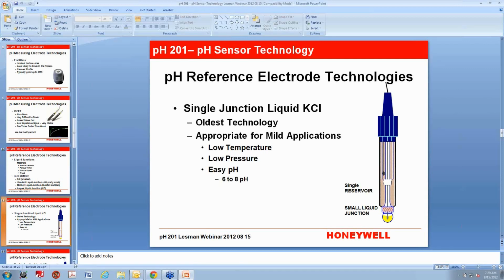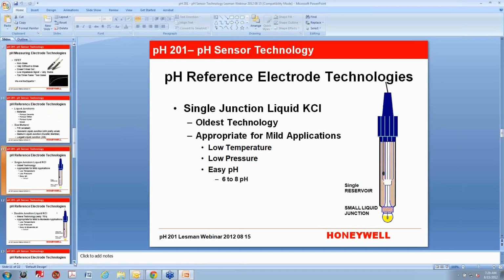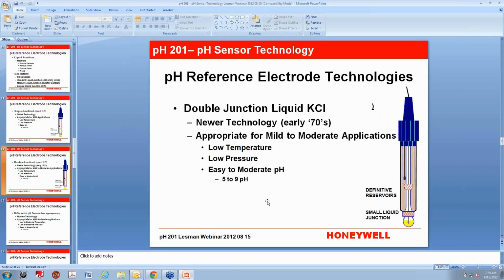Now, the next step that was taken in this technology was to go from a single junction to a double junction. Basically, it's still a liquid junction. This is a little bit newer technology. Instead of just having your liquid junction at the front of the sensor, they'll have a tube with potassium chloride with that liquid junction, and then a second tube inside, so it's completely enclosed with the second liquid junction. I've even seen triple junctions. The idea is that the junctions slow down the migration of poisoning process particulates and ions into that area, because once you get process fluid around the reference electrode, the sensor stops having a stable voltage. You start seeing drift, and you have to throw the sensor away.